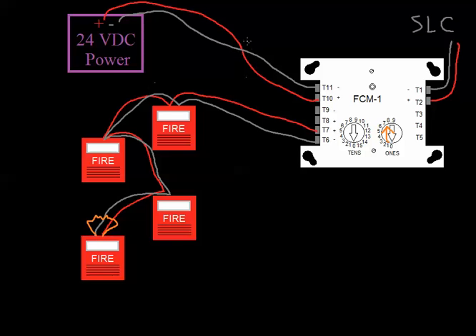But the power up here, that's a little bit tricky. In the old days, we would have to use a power supervision relay like we did for a 4-wire smoke detector because this power terminal was not supervised in any way. And I think I'm going to draw that quickly. But the newer panels now, they have, with updated firmware, they know that based on the type code that you name this thing, if you tell it it's a control module that's going to have a strobe or something that should have 24 volts present at all times, it's going to supervise for that. And if that 24 volts disappears, you're going to get a trouble that says module 8 power loss or power monitor or something like that. But in the old days, you'd have to have, if you had several of these in a line, at the end of the line, you'd have to have the power supervision relay.